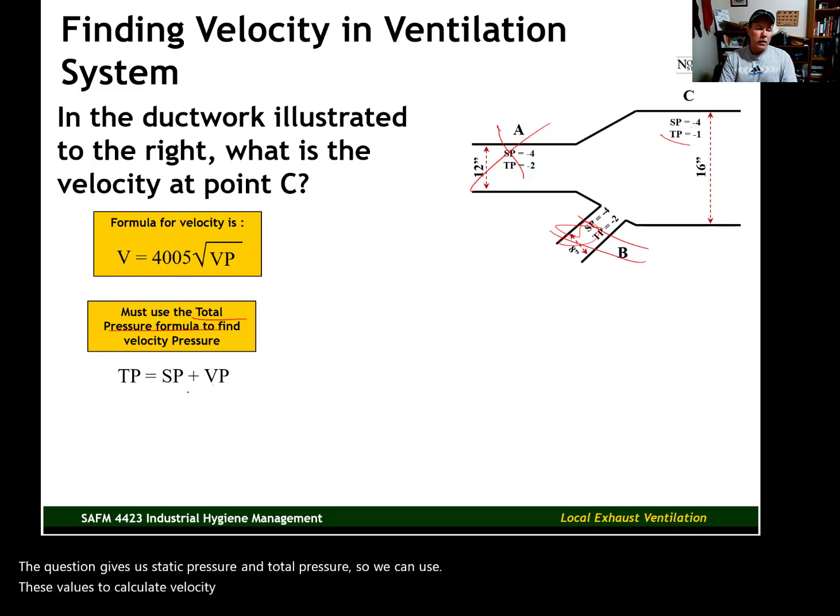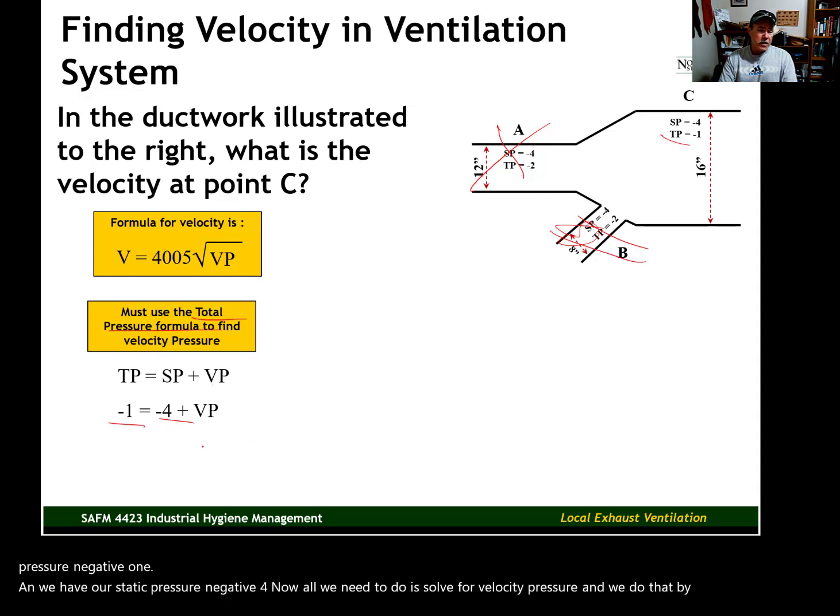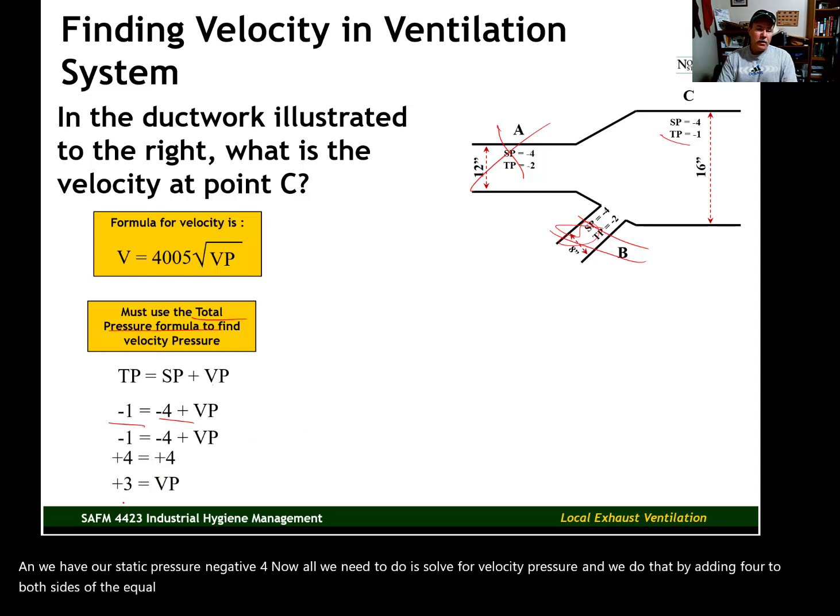Let's just go ahead and plug in what we do know into this formula. We have our total pressure, negative 1, and we have our static pressure, negative 4. Now, all we need to do is solve for velocity pressure. We do that by adding 4 to both sides of the equal sign. When we do that, there it is. Very simple. Our velocity pressure is 3 inches of water column.